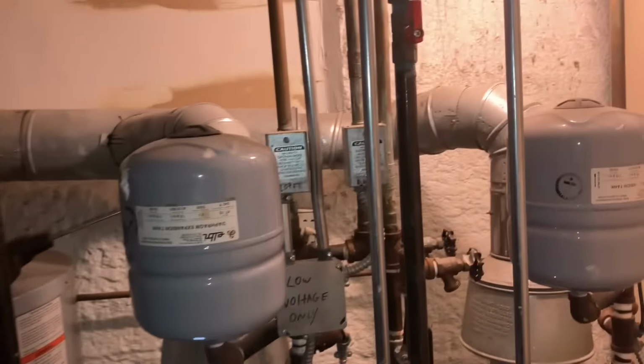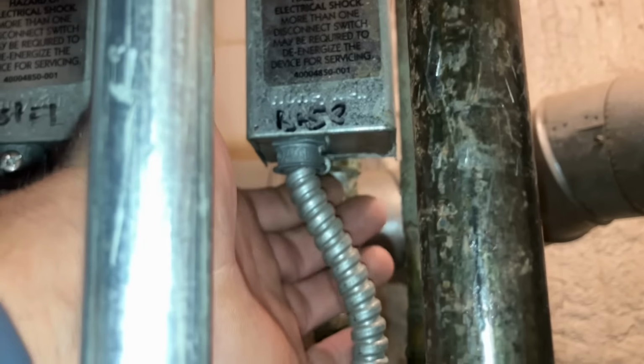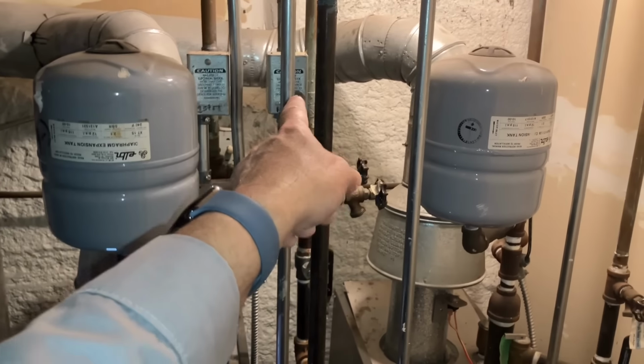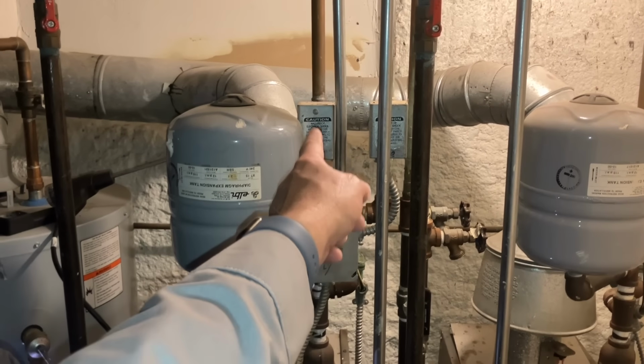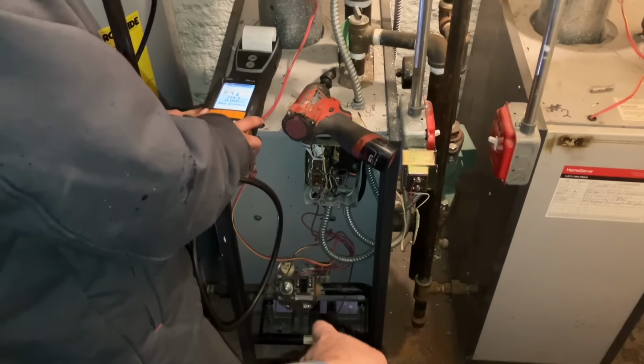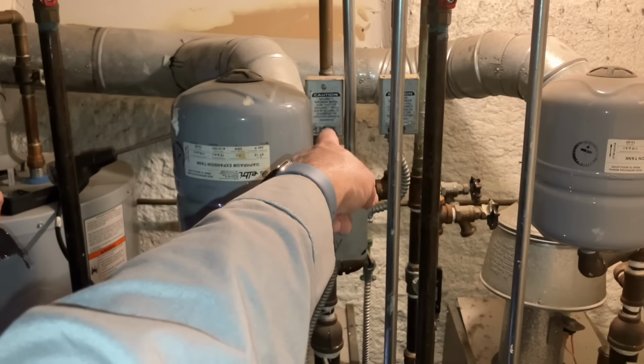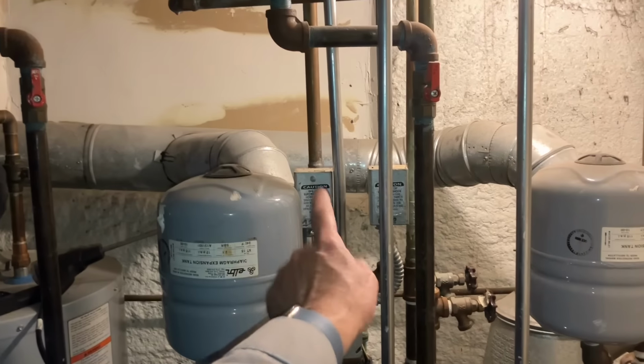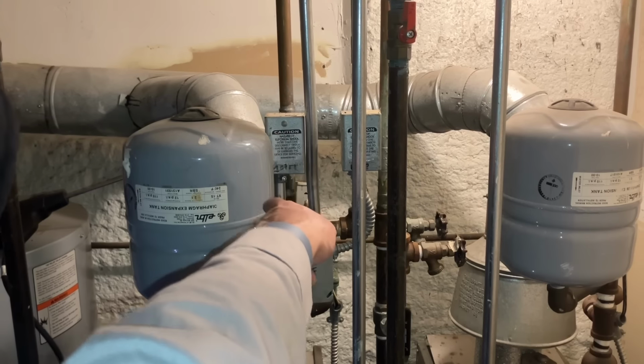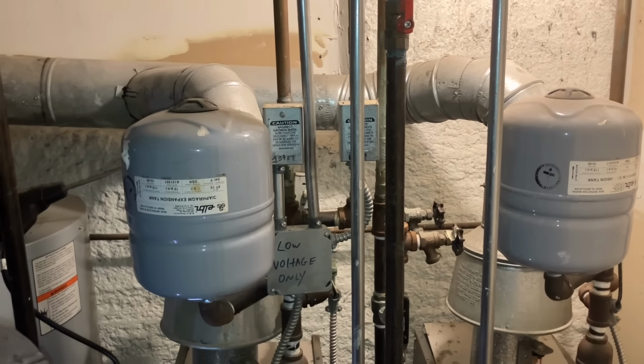All right, so I just lowered the thermostat on the basement zone, and that now has resistance, and that proved that the end switch for the basement turned on the boiler before without the first floor. Now the first floor is on, and the end switch is turning on the boiler as well. So if we had a problem with the first floor end switch and the basement is off, the boiler would turn off, but it's not. So we verified that the end switch inside the zone valve for the first floor and basement are both operational and functional. Finished up the second boiler. Maintenance on that as well.